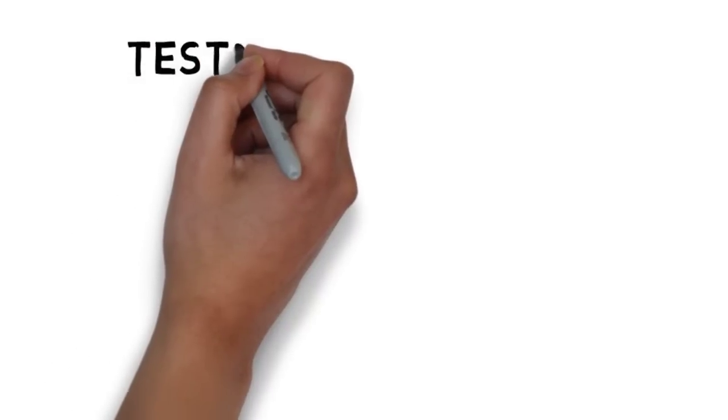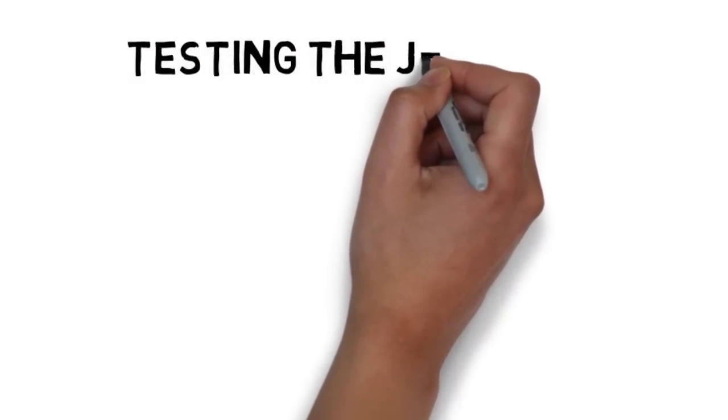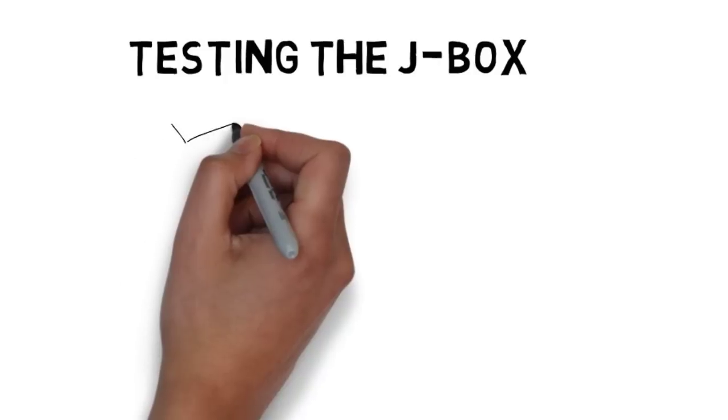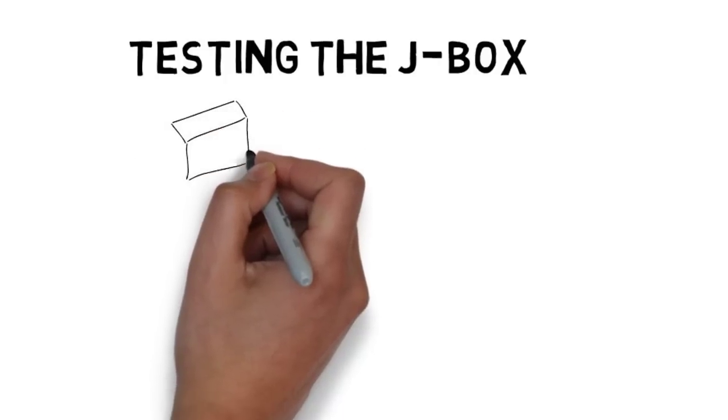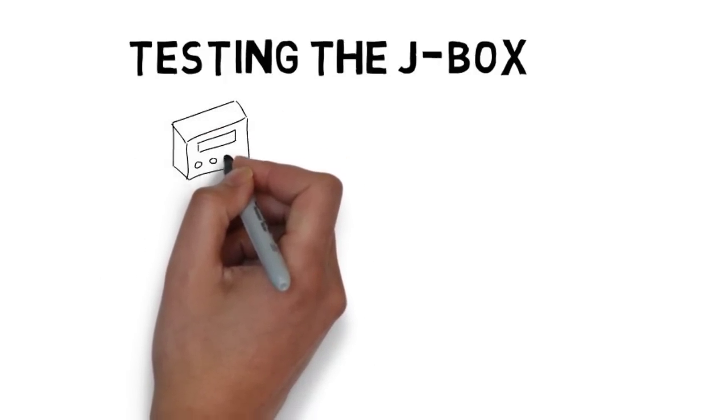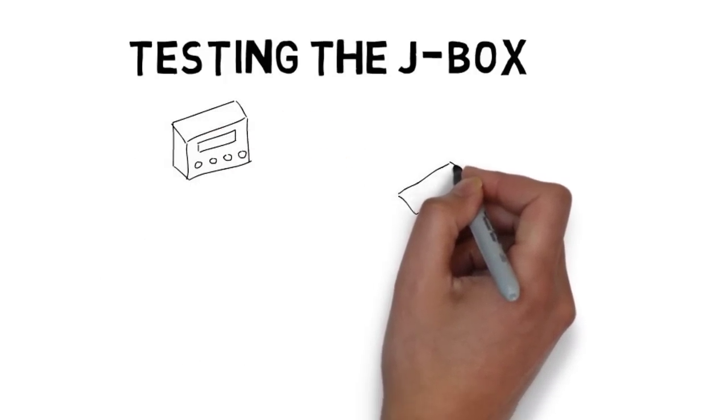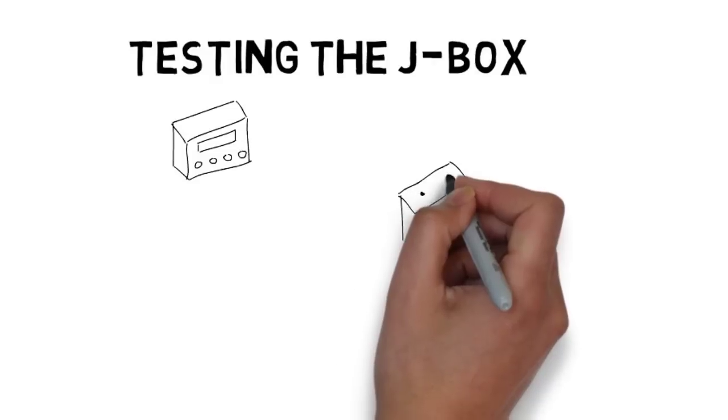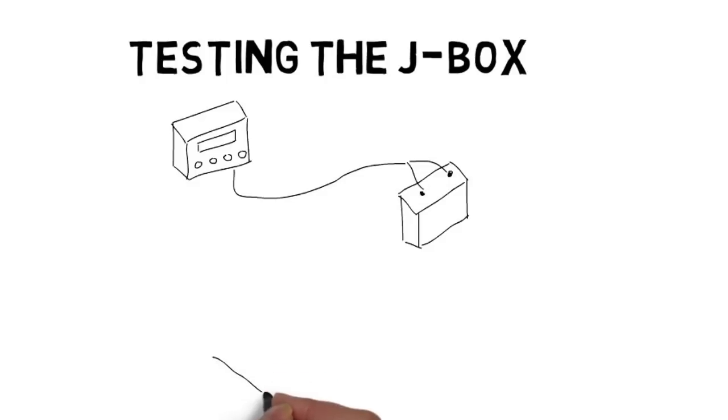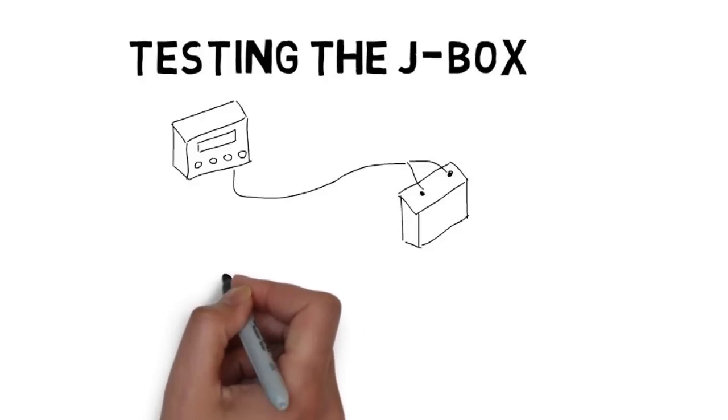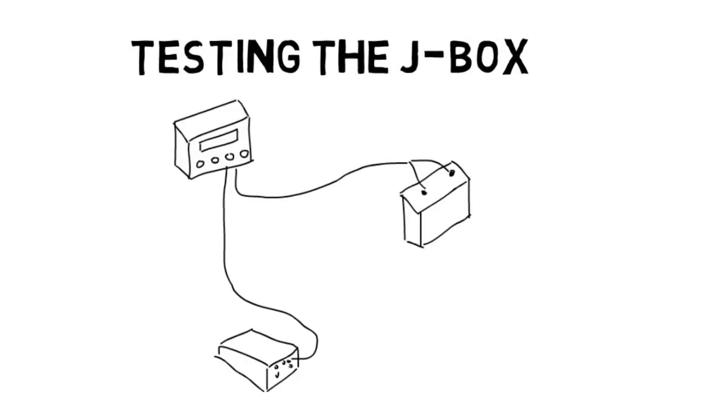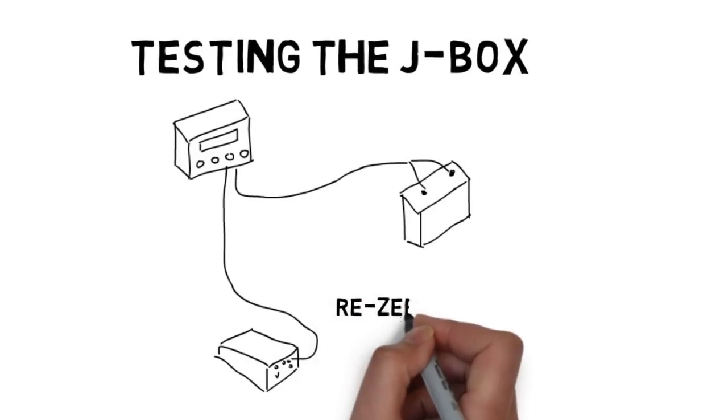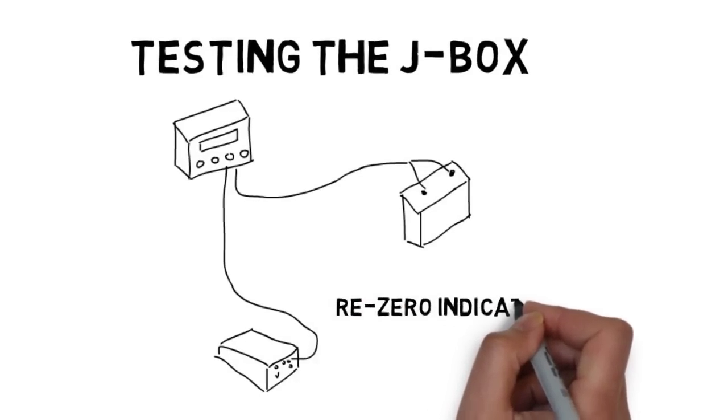To test your junction box, you need to disconnect the load cell cables from the junction box. This is where you may need a Phillips head screwdriver. If you have a circuit board or lever lock junction box, you're going to have to remove the four screws that retain the cover to the junction box. After removing the cover, disconnect all the load cell cables inside the junction box, but leave the junction box cable going to the indicator connected. Once that is done, go back and re-zero your indicator.